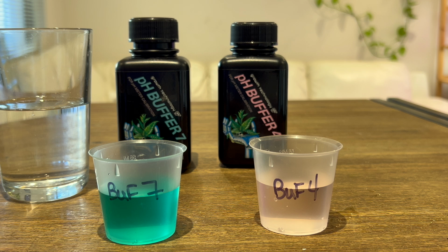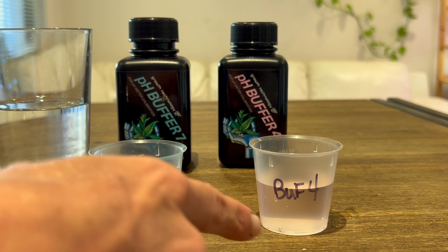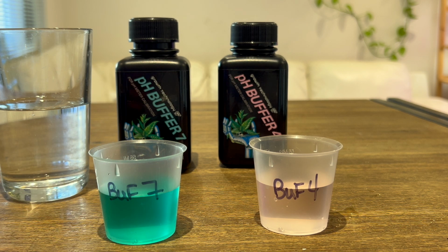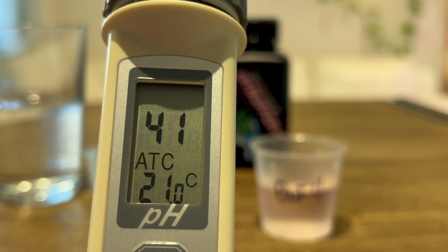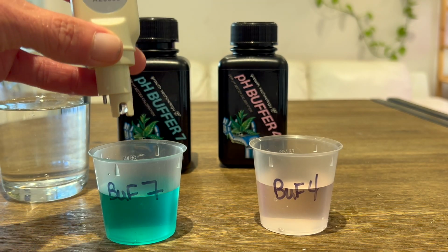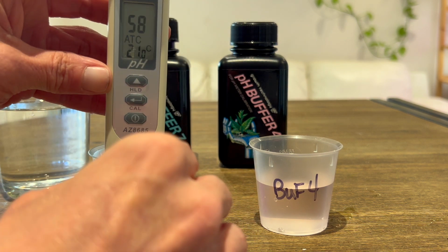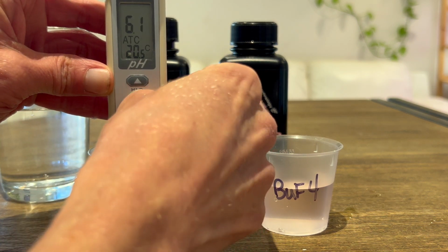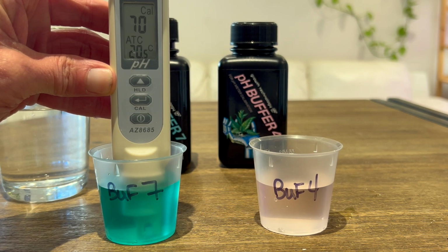Now, some of your pens are going to have a 3-step buffering solution. So they'll have a buff 4, buff 7, and buff 10. This one works just fine with just the 2-step. And again, if you're doing this, make sure you start with pH neutral first. And so what we're just going to do is turn this bad boy on. We can see it's coming on. And now we're just going to stick it into buff 7. And we're going to hit the button that says Cal. And it's going to calibrate itself.